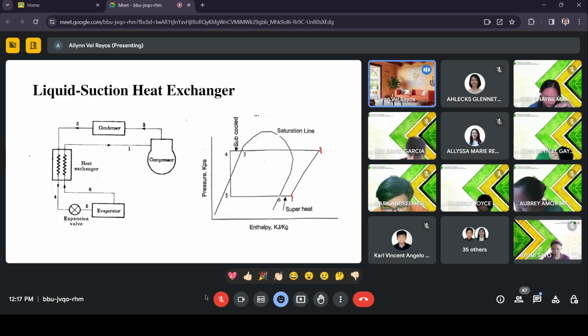So 2 to 3 still condenses into saturated liquid, leaving the condenser as saturated liquid, so HF is still taken there. But it becomes subcooled when it exits the heat exchanger. So here it becomes subcooled in the heat exchanger, and then it enters our expansion valve, 4 to 5, with a constant enthalpy process in the expansion valve.